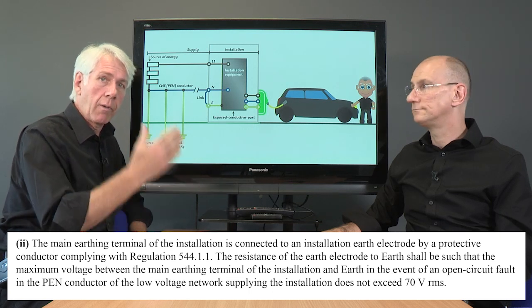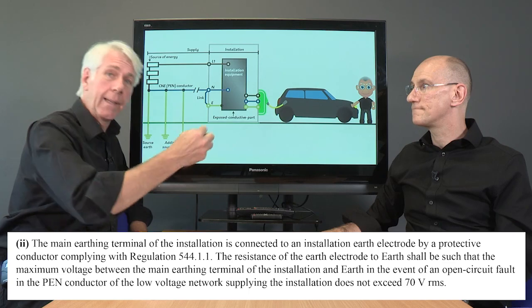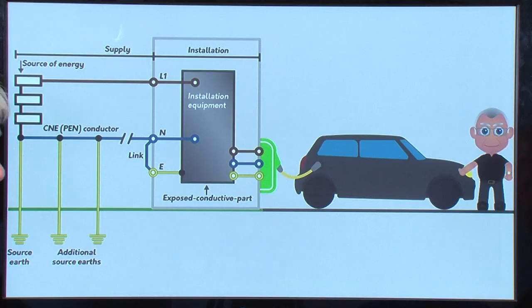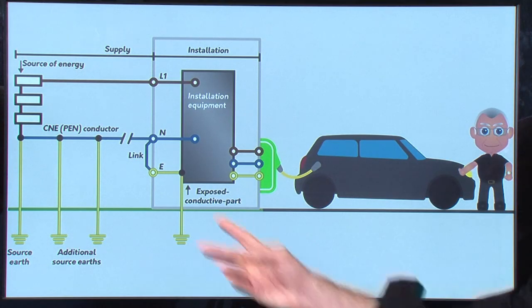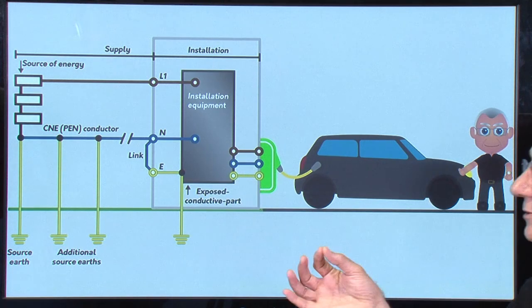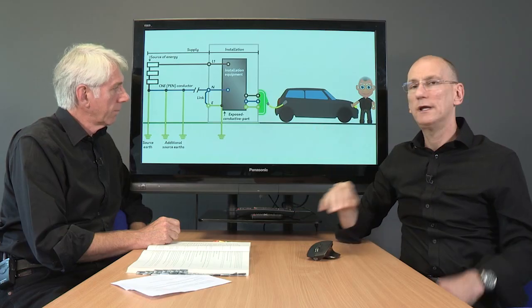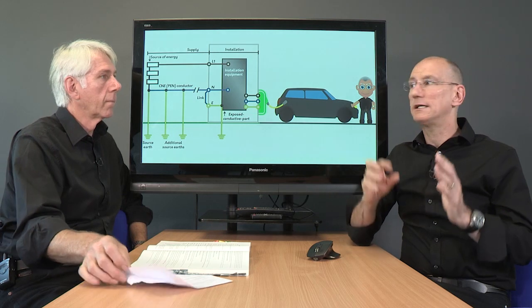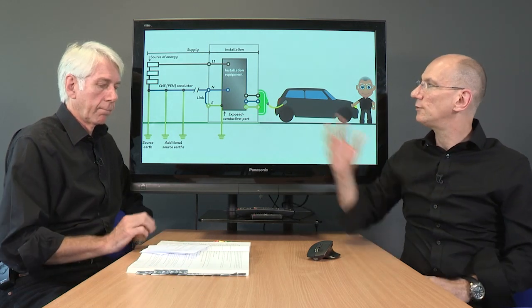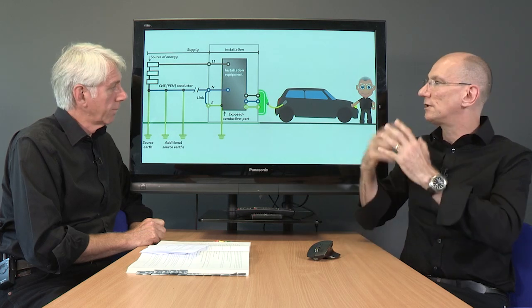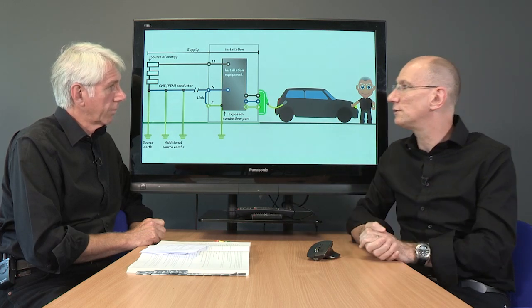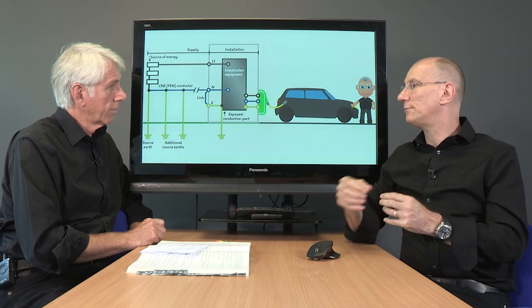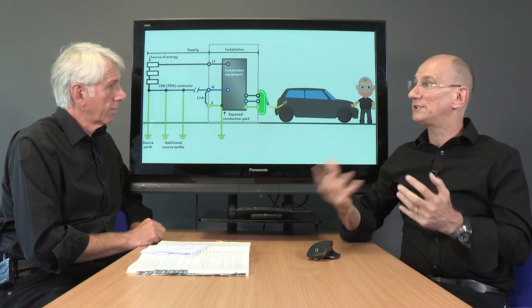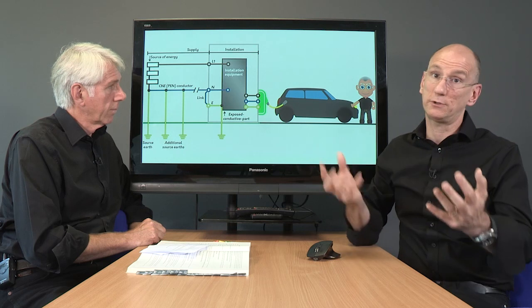Now what we have to do here is draw a clear distinction between that and a TT earth electrode. Yes, and the requirement is for the main earthing terminal to be tied down to an earth electrode at that point. This is still TNCS, not TT. This is to help reduce potentials if you lose the neutral and it just ties everything down. There are other longer term issues to look at with this, so we might have foundation earthing, but because we have lost metallic pipes for gas and water because we've gone to plastic, we've lost all these parallel earth paths.